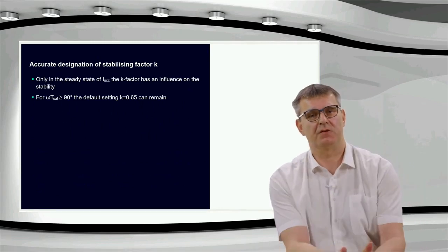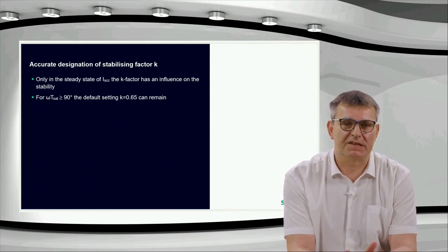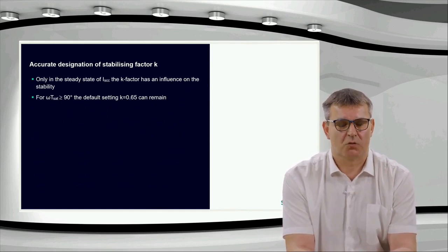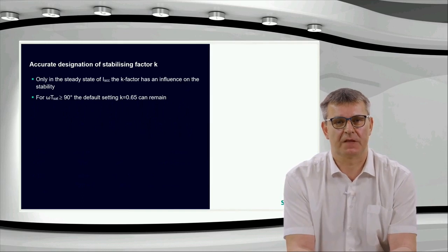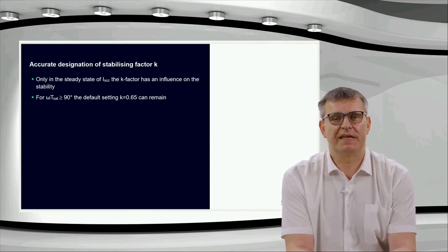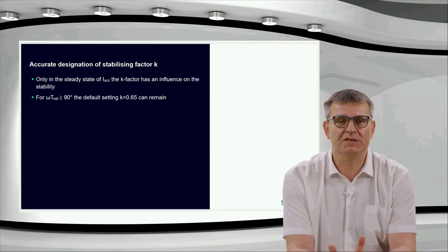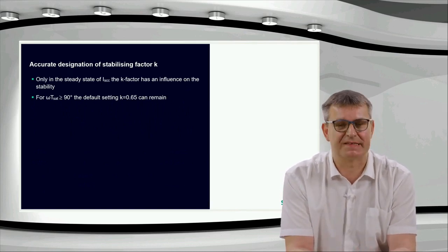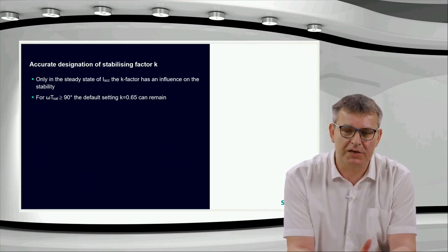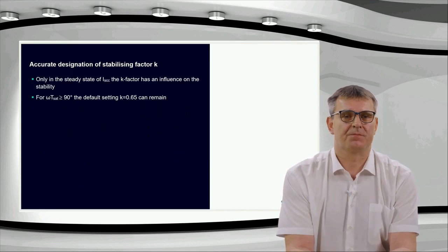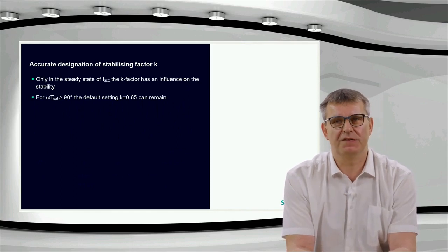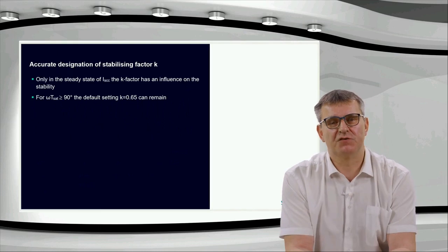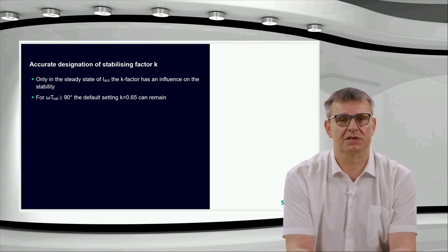Let's think a little bit about this stabilizing factor K. As already said, only in the steady state, when the DC component has declined, the K factor really has an influence on the stability. And that directly leads to the statement I have shown. A wrong tripping in an external fault due to wrong CT dimensioning will occur mostly in the steady state, means it will happen 100 milliseconds after fault injection.